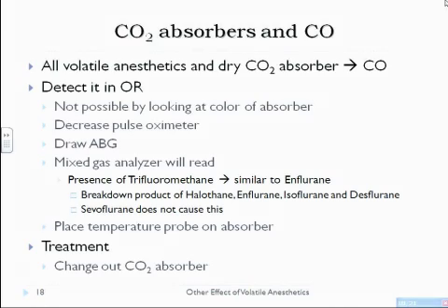If you have a mixed analyzer during the case, what you'll see, especially if you're using desflurane, is that the machine will start saying that it's measuring enflurane. The reason it's measuring enflurane is one of the additional byproducts of metabolism. It's a conversion of something called trifluoromethane, and to a mass spec or a spectrometer, trifluoromethane looks like enflurane, so it begins to give you this mixed read. If you're seeing that, that patient most likely is getting some kind of metabolism taking place in the CO2 absorber, and you should change it out. And I would recommend you do that immediately, as soon as possible.